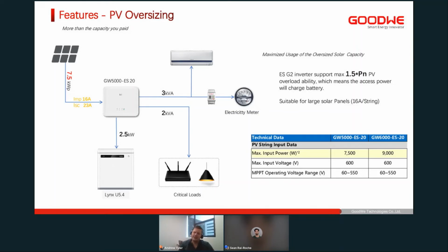With this 5 kilowatt inverter and our 7.5 kilowatt PV array, you can see that we're running 3 kVA to our on-grid load, which in this scenario is an aircon. We've then got a 2 kVA load going to our critical load or backup output. That's a total of 5 kVA. Typically, that's where it would stop, but we've got the benefit of being able to use the other 2.5 kilowatts to charge our batteries simultaneously. So even if you are constantly using 5 kilowatts, you would still have excess PV to charge your batteries, which gives our system quite a benefit and an advantage, because in essence, you've got a 7.5 kilowatt PV inverter and a 5 kilowatt backup inverter in this specific case.